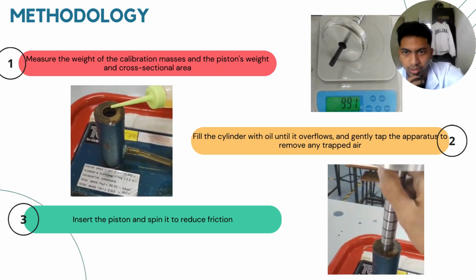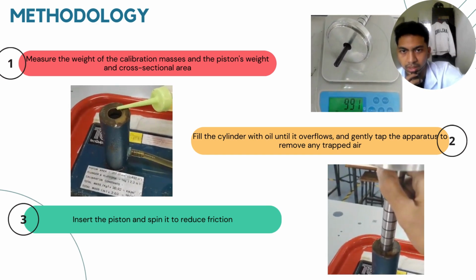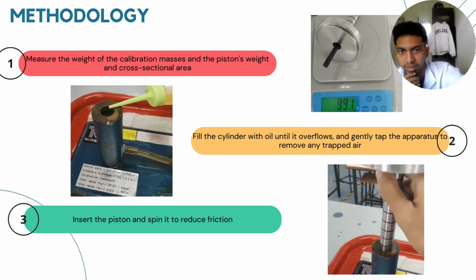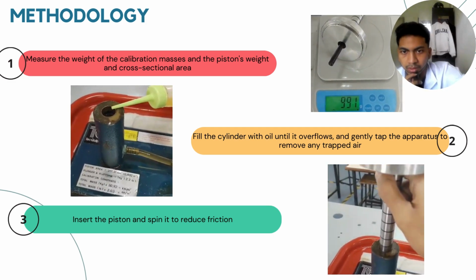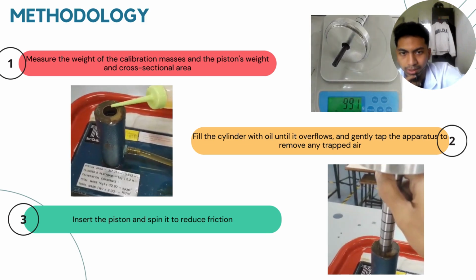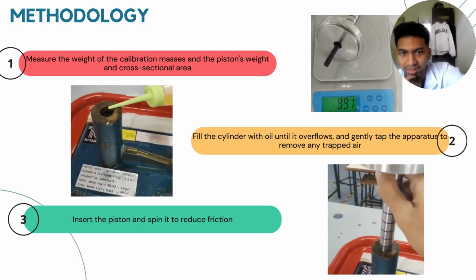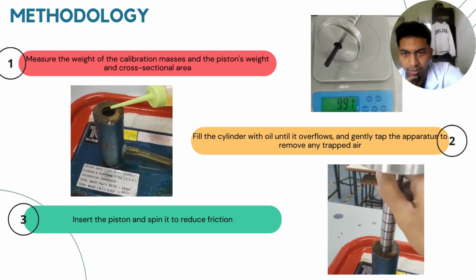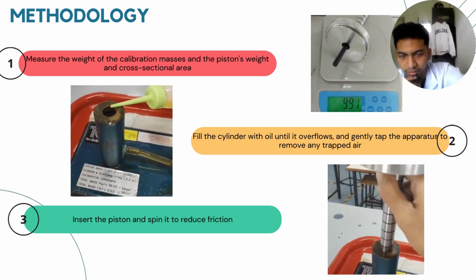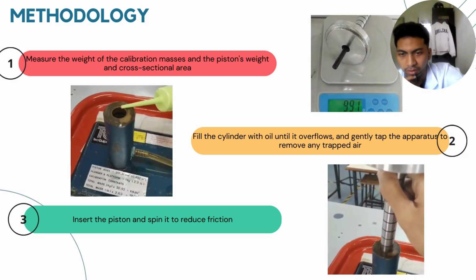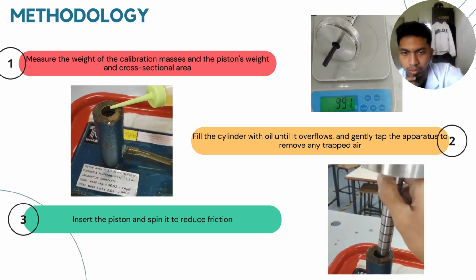First, we have to measure the weight of the calibration mass, the piston weight, and the cross-sectional area. Second, fill the cylinder with oil until it overflows and gently tap the apparatus to remove any trapped air. Third, we insert the piston and spin it to reduce the friction.